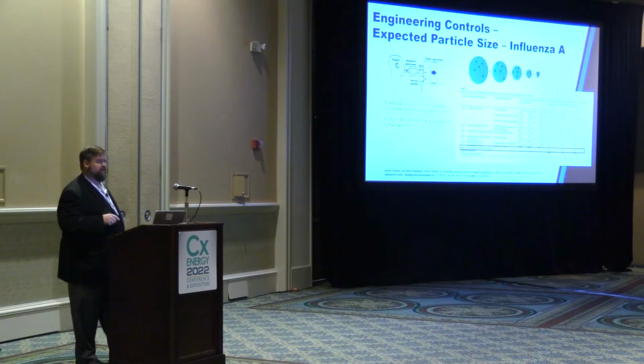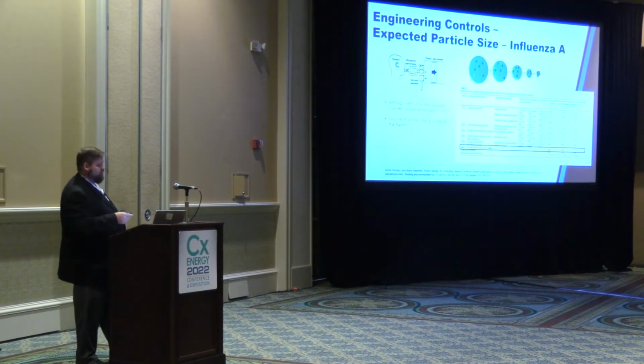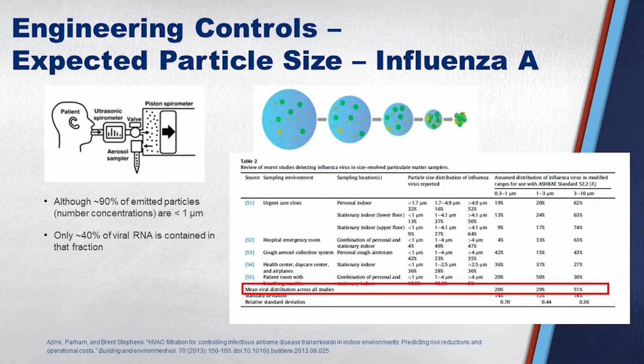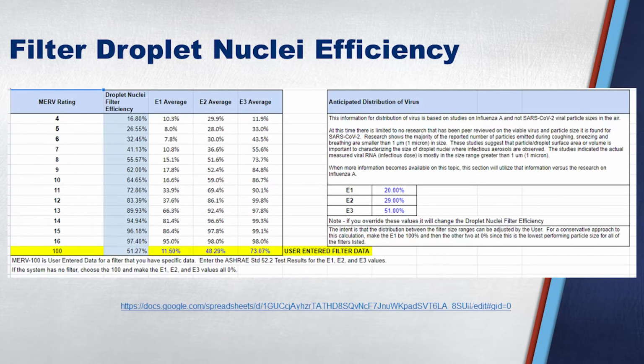At the time we built it, there was very minimal research on SARS-CoV-2, there still is, but there was a lot of research done on influenza A. In essence, Stevens and Azimi compiled all of these studies that evaluated where those particles were. What's great is they were able to get the study data and put it into ASHRAE standard 52.2 buckets, so the micron size. These three columns are the different size ranges for 52.2. Now, if I've got a percent of where that filter in each one of those buckets can pull from, I can actually get a single value, right? They referred to that as filter droplet nuclei efficiency. Really easy term to remember. The results of their study were 20, 29, and 51, from smallest particle to largest particle.